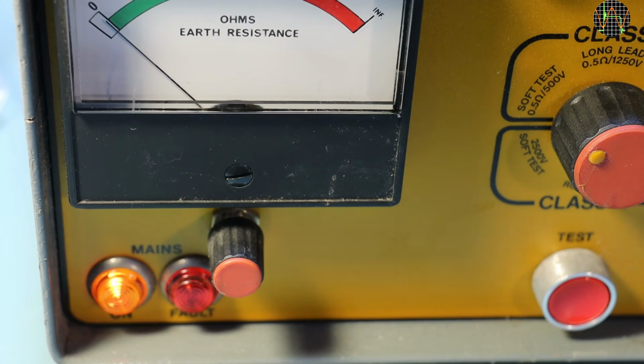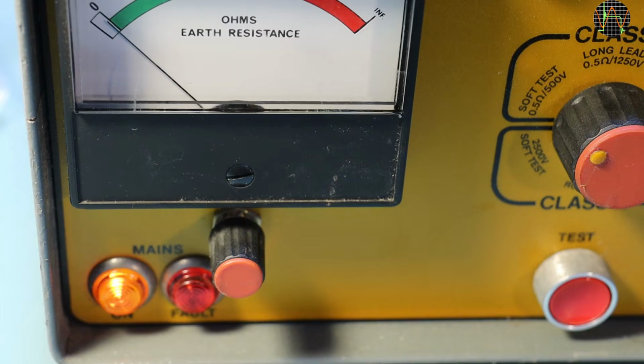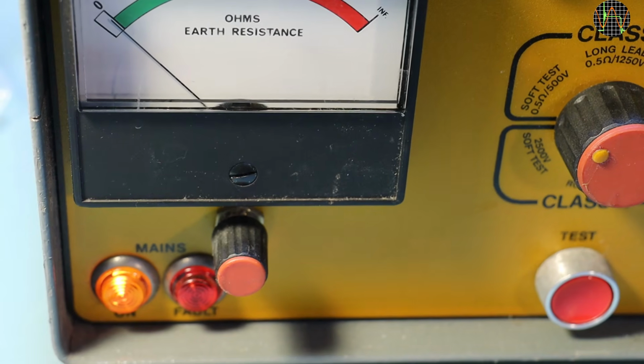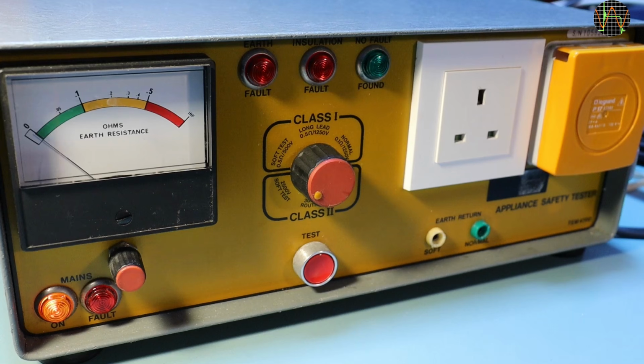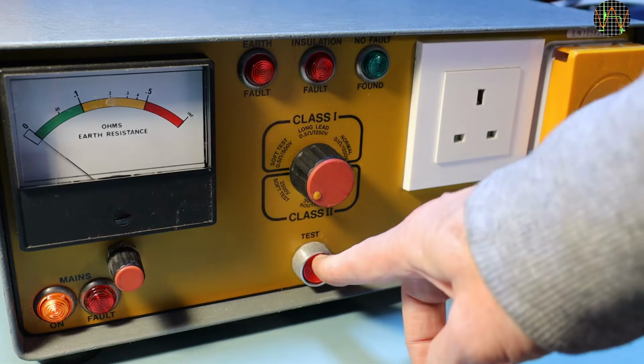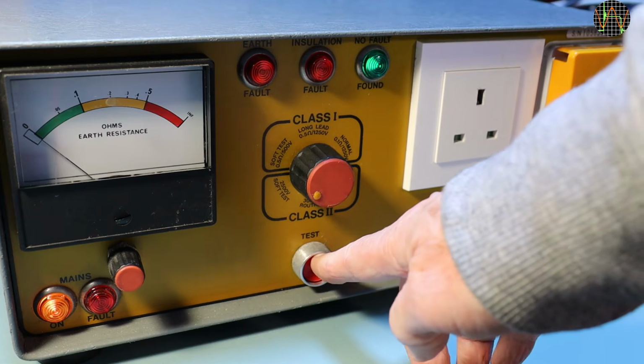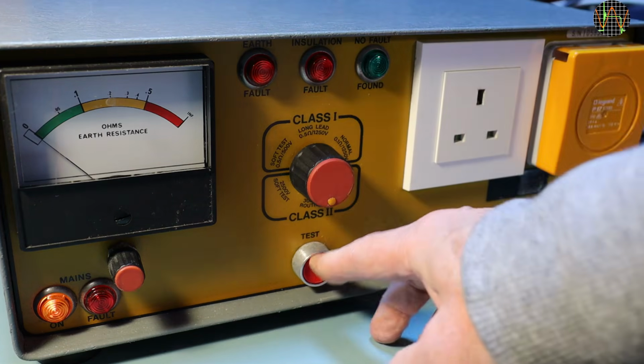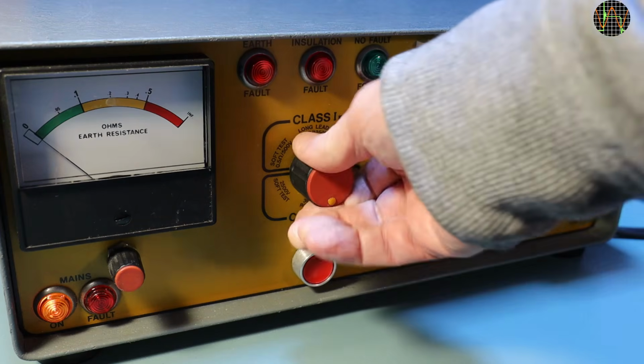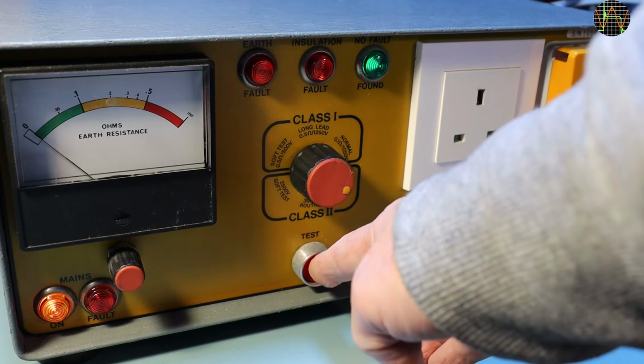Because there is no power switch, the on light lights up immediately. At least the fault light doesn't illuminate, which is encouraging. With nothing connected to the sockets on the front panel, let's run some tests. First, going to the class 2 settings. I expect all these to pass, showing a green light, because the only test is insulation, and with nothing connected there should be no problems in passing, unless there would be an insulation fault inside the tester itself.